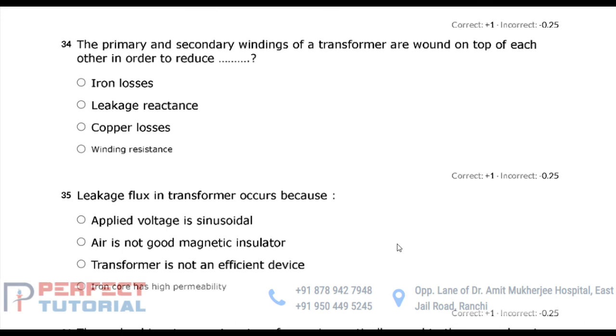Primary और secondary winding को एक दूसरे के ऊपर wound किया जाता है. That is particularly in case of a core type transformer. That is particularly to reduce the leakage reactance or simply to reduce the leakage flux and hence to improve the power transfer capability of transformer. So the correct answer is leakage reactance.